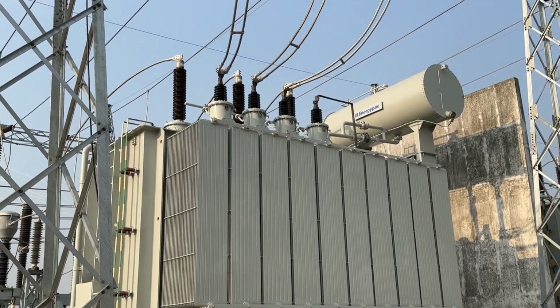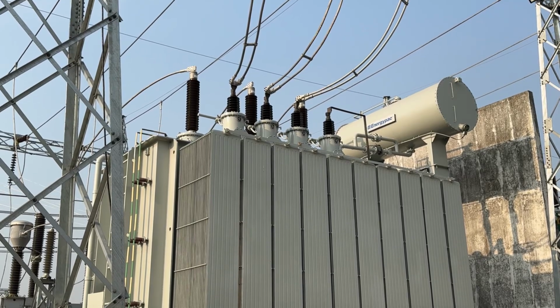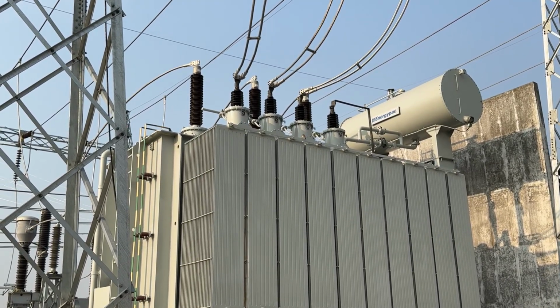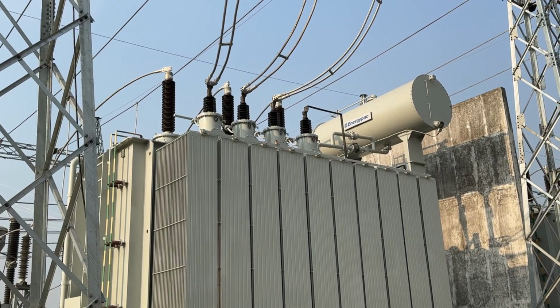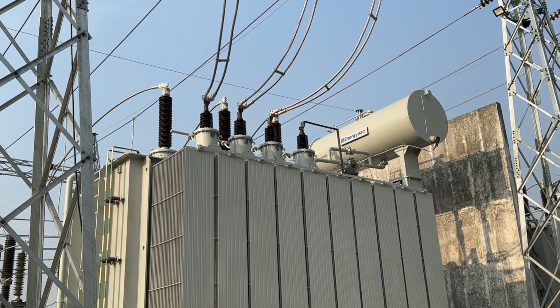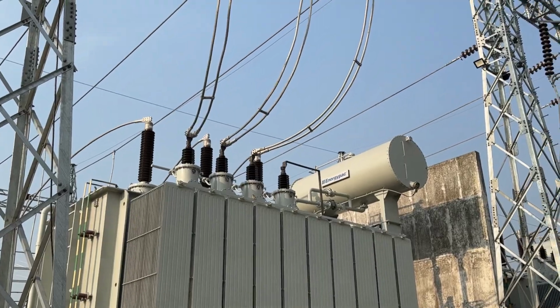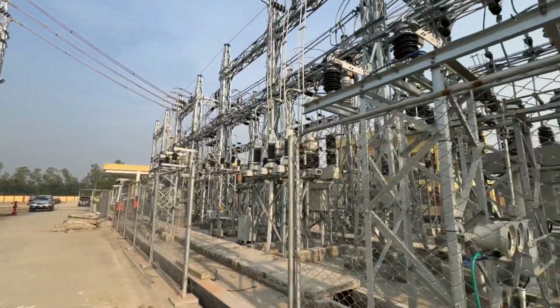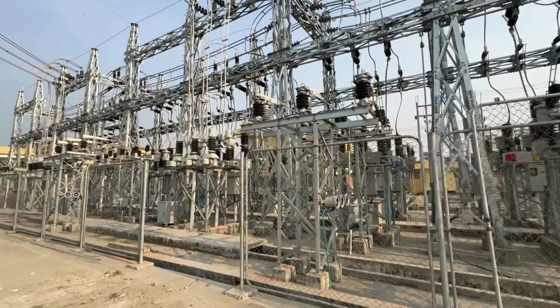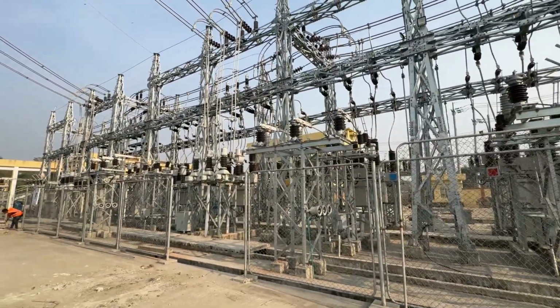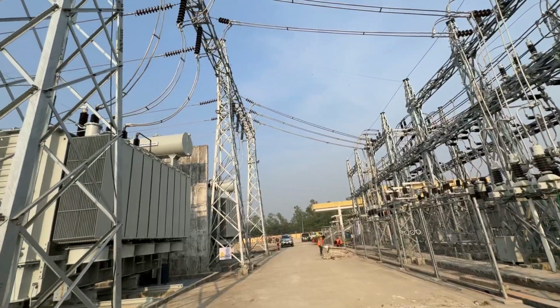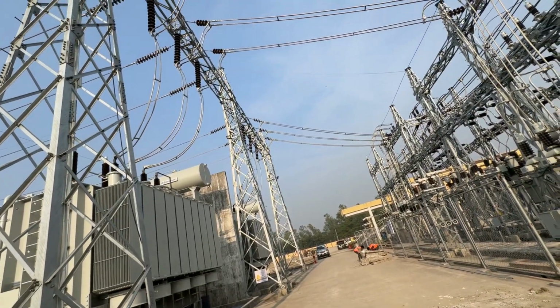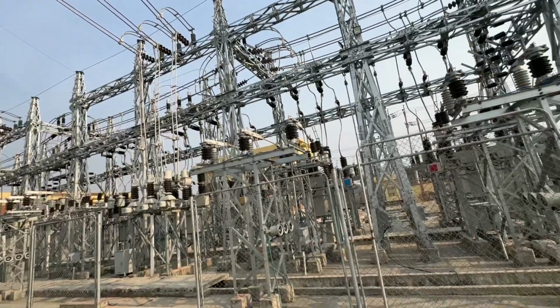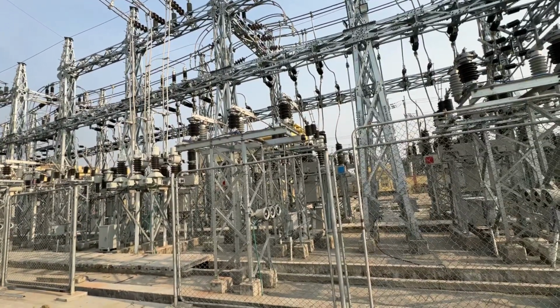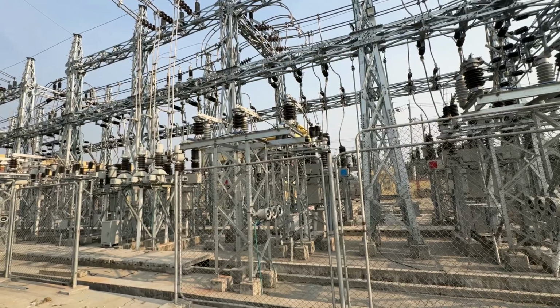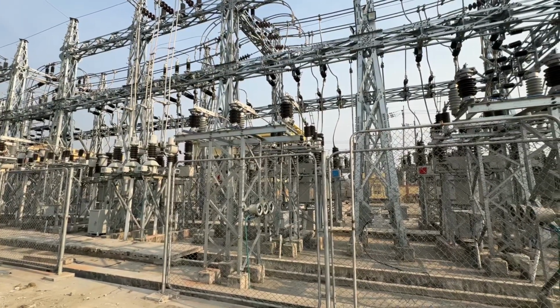There are two types of bushing on the transformer. The long height bushing is the 132 kV, and the short bushing is the 33 kV side bushing. And this is the 33 kV switch yard. The output of the two transformers came to this substation, and there are so many, I think 15 to 16, 33 kV distribution feeders here.